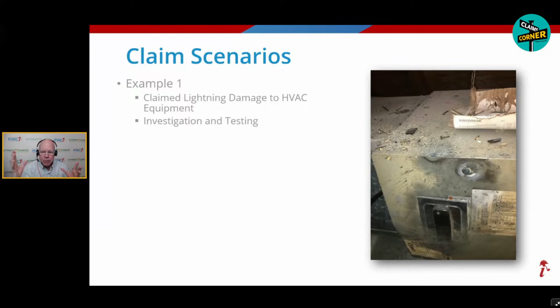That's not surge. That's definitely lightning. Got some fried wires as well. So you guys know the outcome on this one, right? We're going to replace the thermostat on system 1 and the entire system 2, because now we have air handler damage in the attic. We have wire damage. It traveled all the way through the wires back outside to that condenser outside as well.